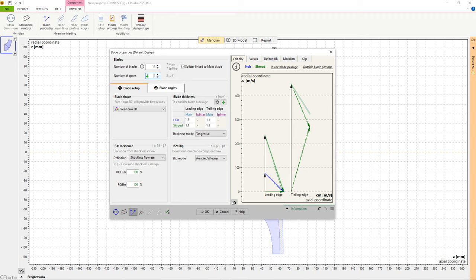At first, we set the number of blades and the number of spans. Then we choose a blade type for our application. In most cases, this selection is determined by the manufacturing method of the impeller.